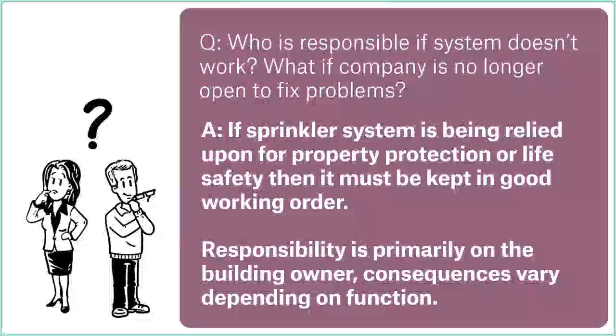But where the sprinkler system is being mentioned, say, as far as the fire safety of the building, you've got your safety file, and you say, we've got a sprinkler system here, and we're relying on that either for property protection or for life safety, then, of course, it has to work. Otherwise, you're basically making it worse. You're saying the building's safe because you've got a sprinkler system. Well, if it's not working properly, then arguably the building is in a worse state than it would be before. If you knew you didn't have a sprinkler system, then you might be looking at other means to improve it.